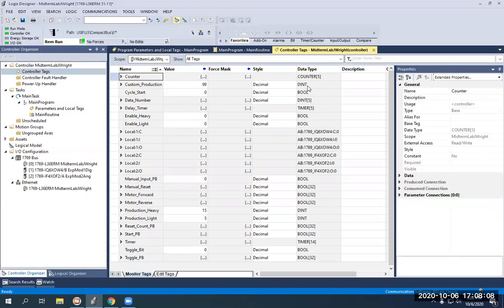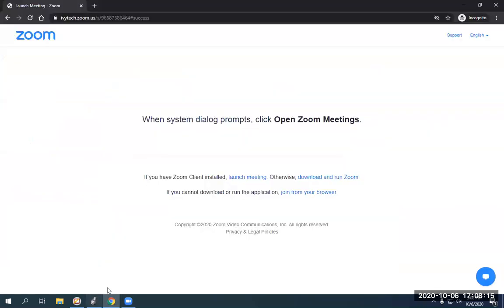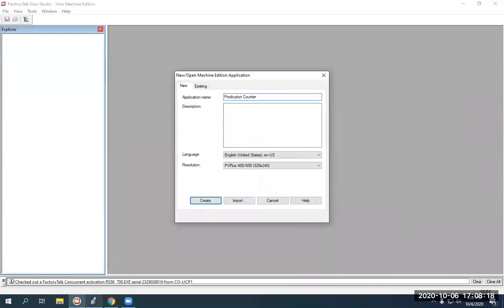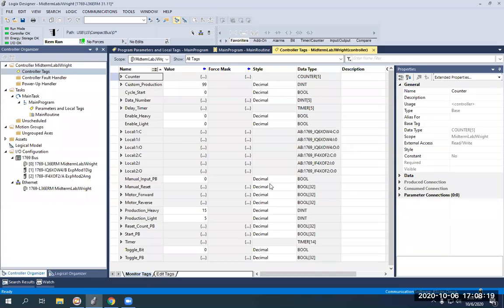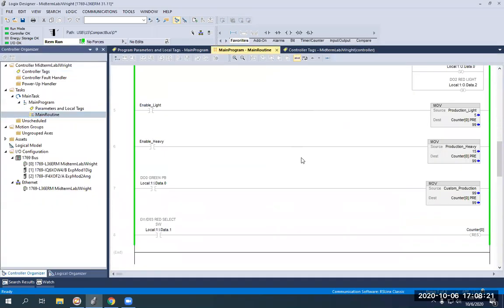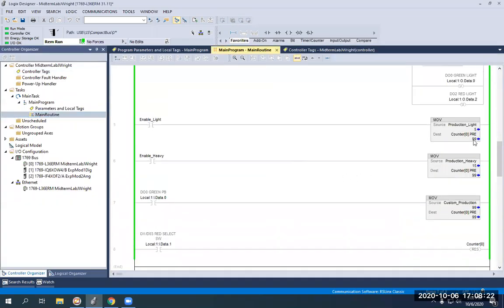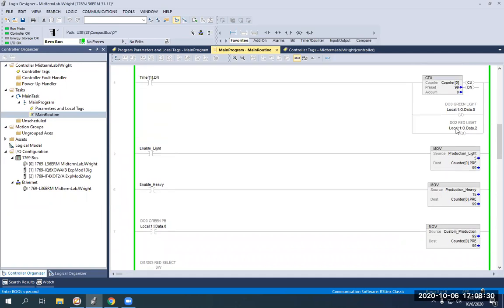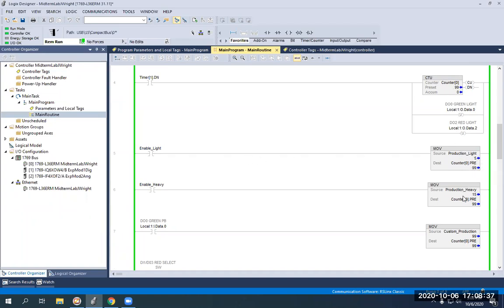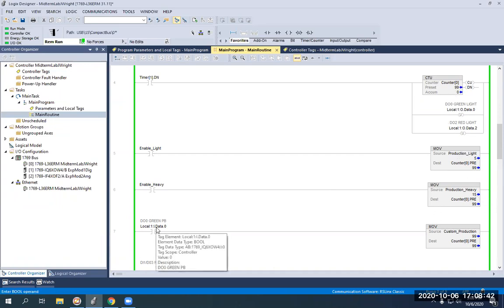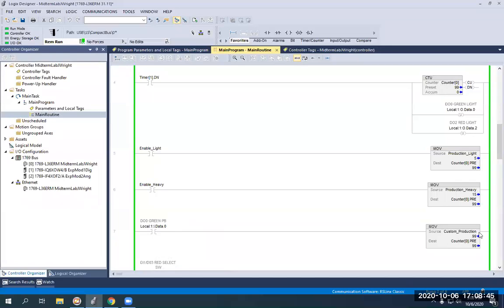Now the data integers are going to be used in conjunction with the numeric input enables and numeric displays and our move bits within our program. So you can see going back to my program, all of our move functions have those numbers associated. So when these associated Booleans or these inputs enable those move functions that will change our counter presets to whatever is in there. So enable light will add five to the preset, enable heavy will move 15 into the preset and my green push button will move whatever my custom production is. Now custom production is going to be available on the HMI in the form of a numeric input enable bit.